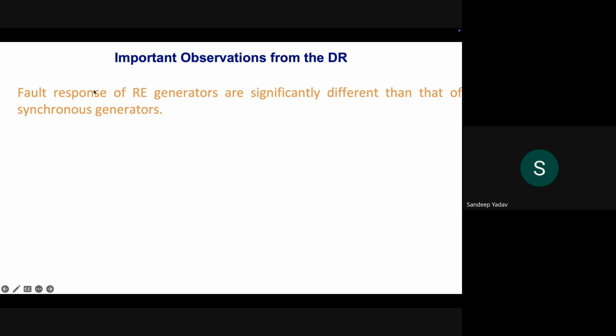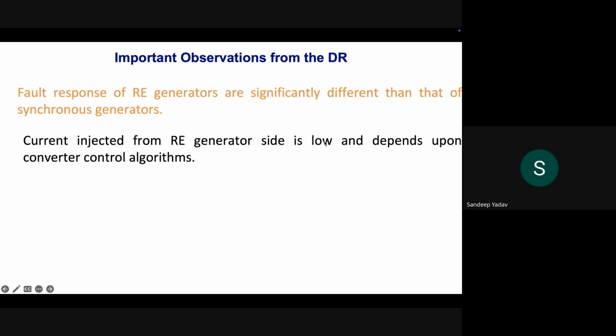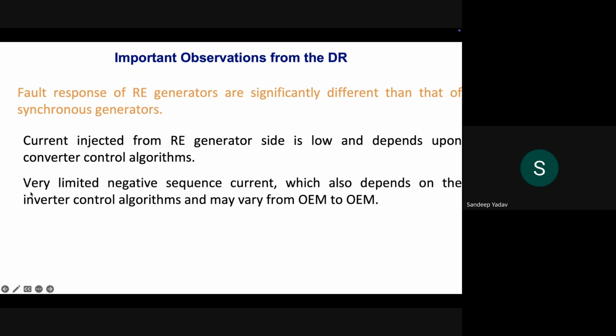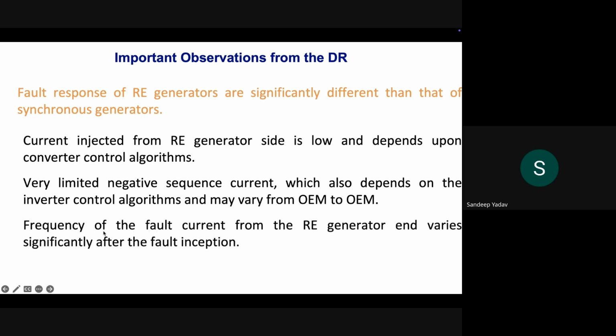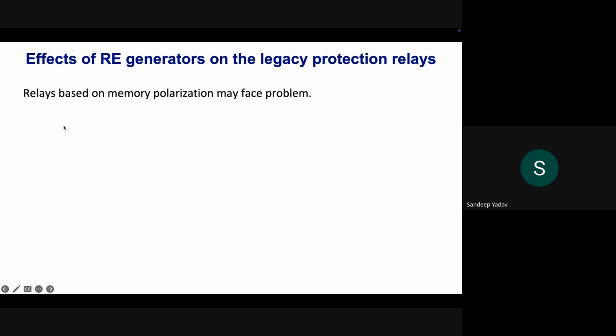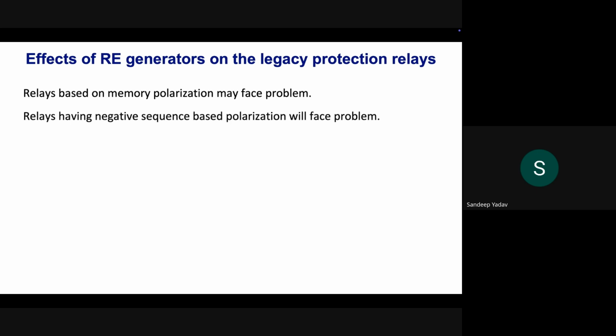So we saw that the fault response of RE generators is significantly different from synchronous generators. The current injected by the RE generator is considerably low, and it may depend on the converter control algorithm, and it may change from one manufacturer to another. Very limited negative sequence current injection, which also depends on the control algorithm from OEM to OEM. Then the relays which are based on memory polarization may face problems when it comes to detecting the direction of the fault. Relays which work on the basis of negative sequence polarization will also struggle.